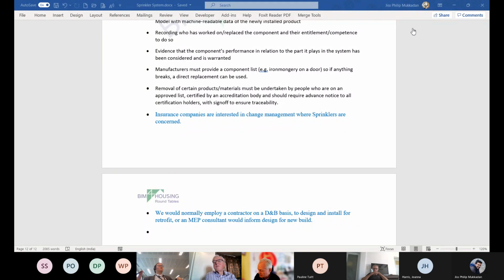Rather than you come in the front door and you can see the living room, and then beyond it is a bedroom, which is what people want. Now that's allowed with sprinklers and enhanced detection. And if you now know you're going to be putting the sprinklers in anyway, you can design like that, whereas previously you didn't.